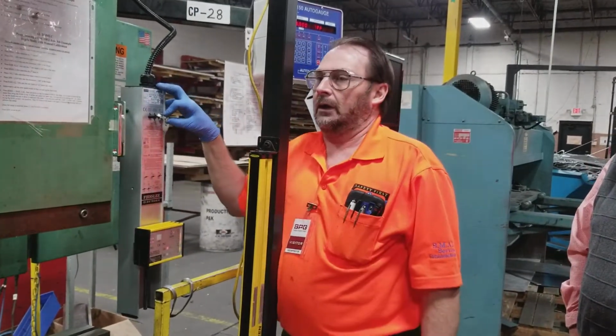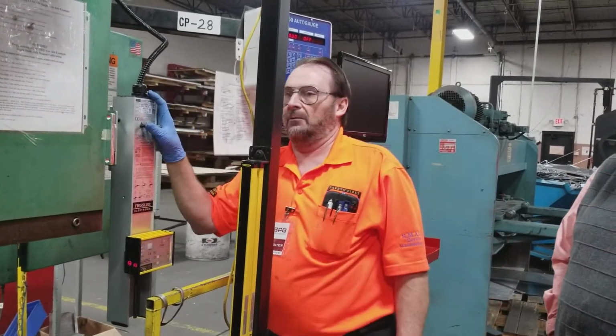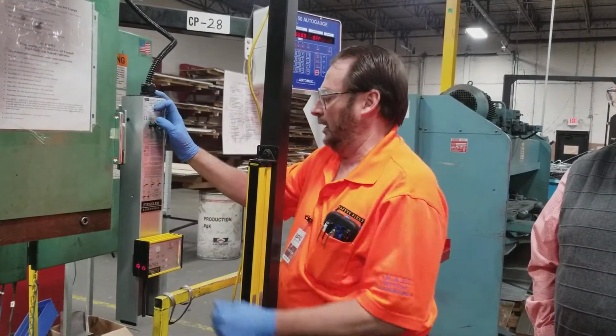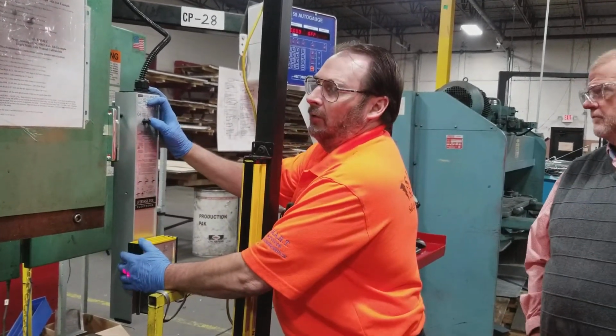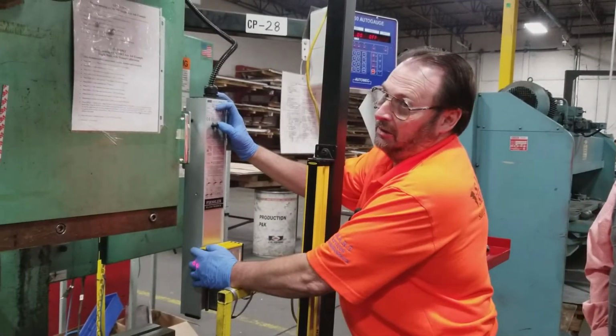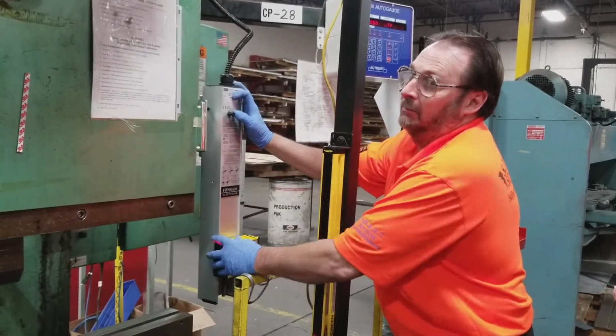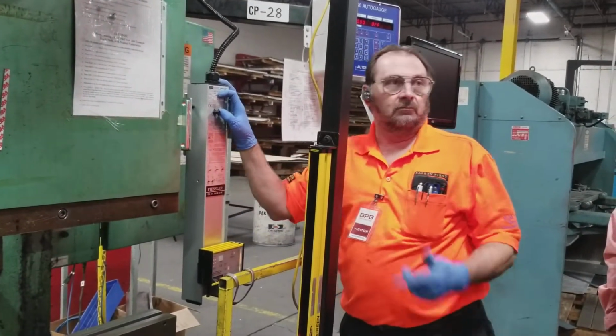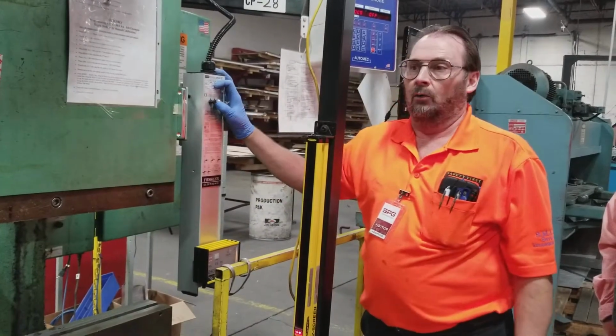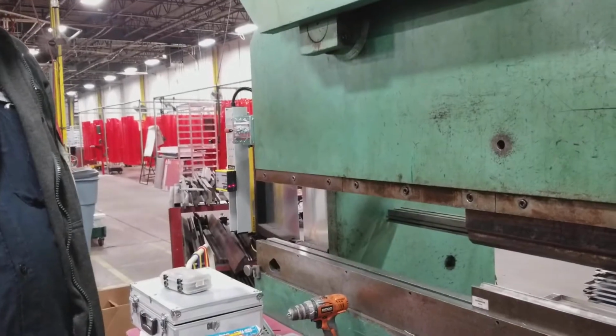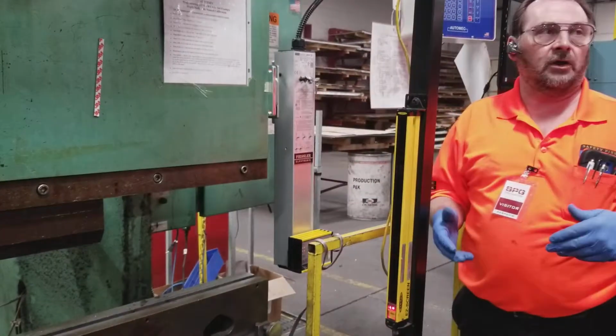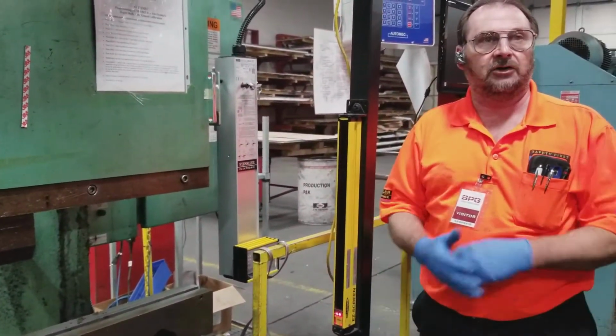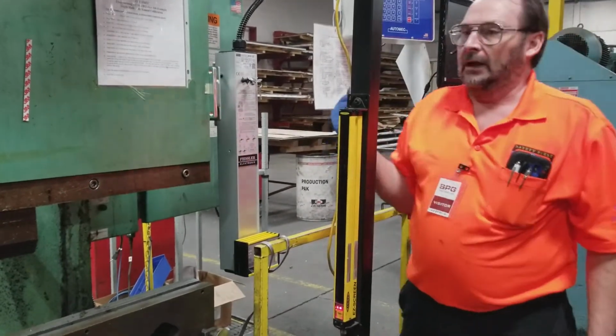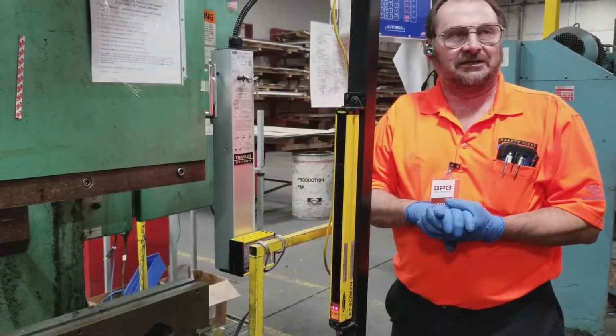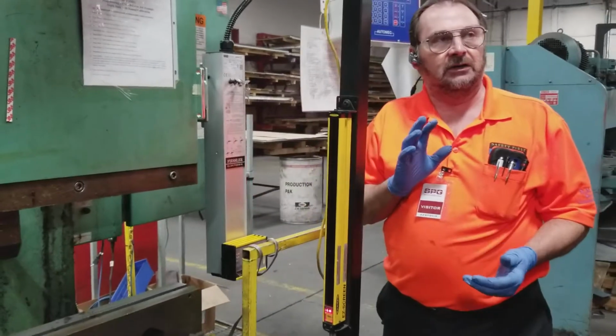All right, let's say that we're calibrating and we forget we're calibrating. We interrupt the laser as it's calibrating, either moving the tooling around, moving parts around, or maybe working with the back gauge. What you may see is something similar to this: you'll have one all the way down to the bottom, one all the way to the top, or they may both be all the way down to the bottom. What it's done is it's lost its sync, so we have to bring it back into sync.